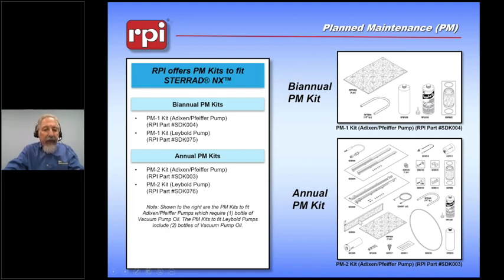We also have an annual kit, it's called the PM Kit 2, that also contains the biannual kit, allows you to do the oil change, and includes things like the rails that are within the chamber, which will decay from the exposure to the hydrogen peroxide. We get a new catalytic converter that will break down over time, a new UV lamp, which we want to make sure stays working through the entire year, and a door gasket.